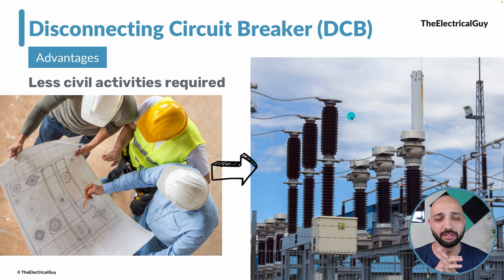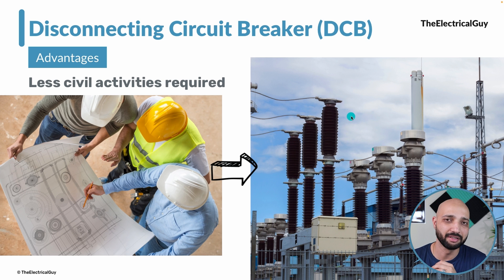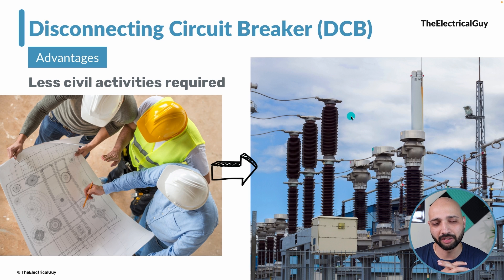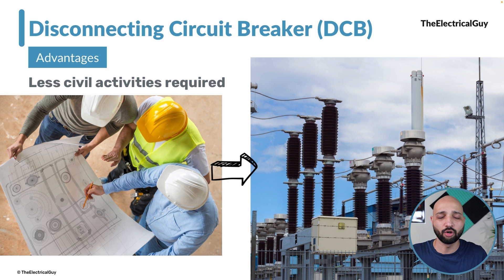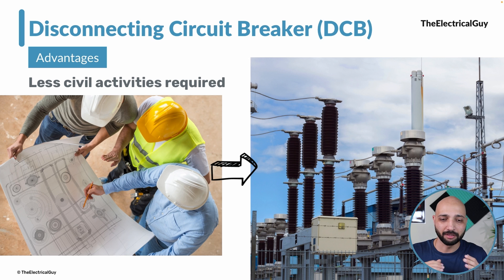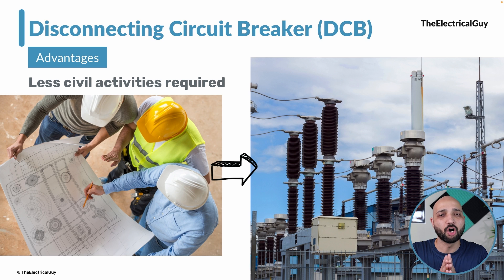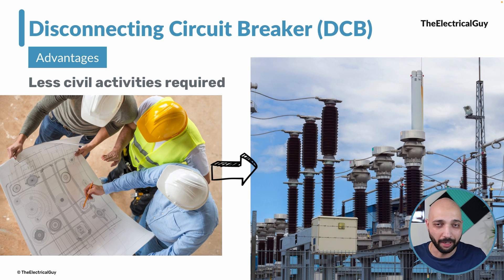Since we are eliminating a dedicated disconnector device, there is also less civil activity required in the substation. With a dedicated disconnector, you need to build a separate civil foundation, then a support structure, and then the disconnector on top. But since the disconnecting circuit breaker combines both functions, it can be fitted on a single foundation, resulting in a significant reduction in civil activities as well.